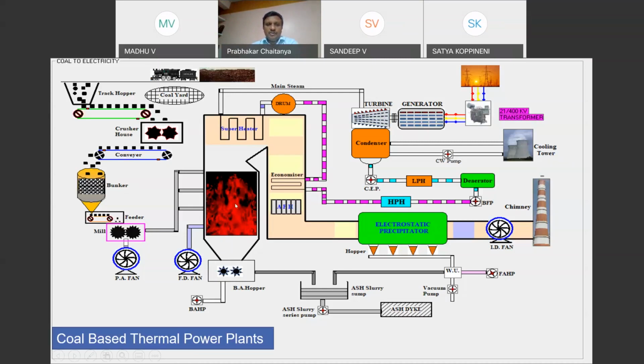Second thing, how can the load of the generator be varied? The amount of steam that we are giving into the turbine will be regulated by the boiler drum pressure. How much pressure we are giving, and at what temperature we are letting the steam go into the turbine, will decide the power generation from the generator. So we need to regulate the coal. Here, this small element called the feeder will regulate the amount of coal flow going into the boiler. If the speed of the feeder is less, lesser coal will be given into the mill and lesser coal will be available at the boiler. If the speed is higher, obviously more coal will be fed into the boiler. That in turn will give the actual load of the generator.